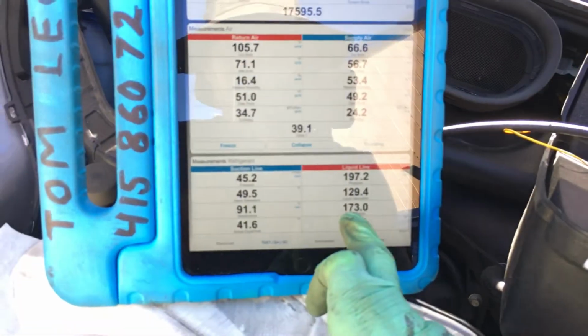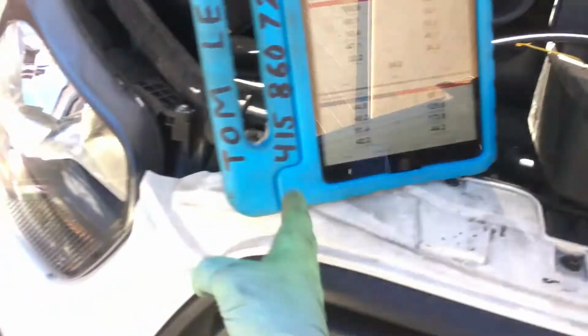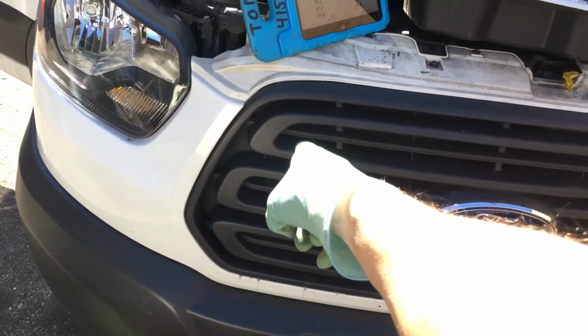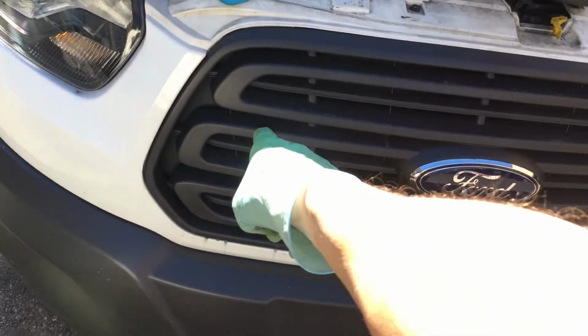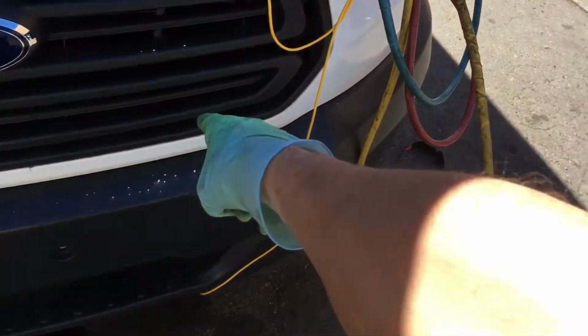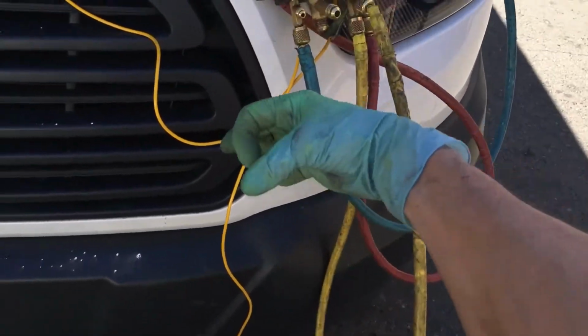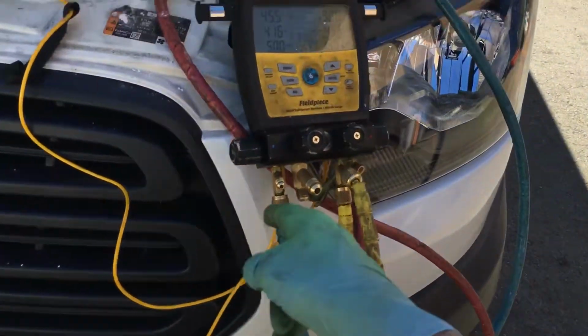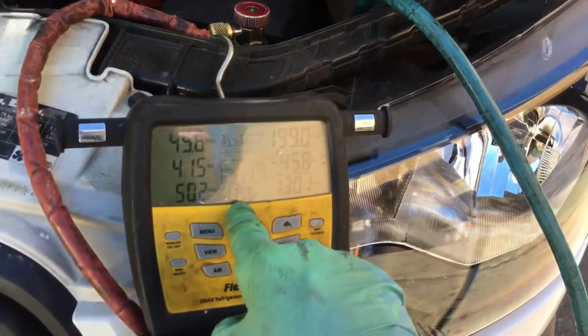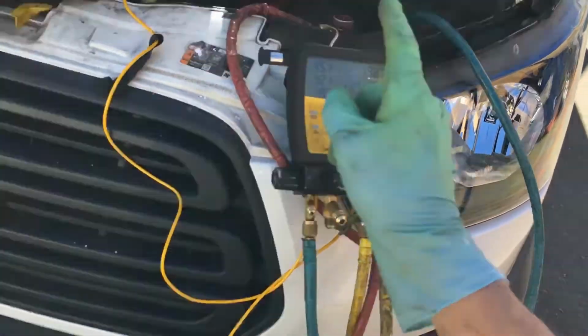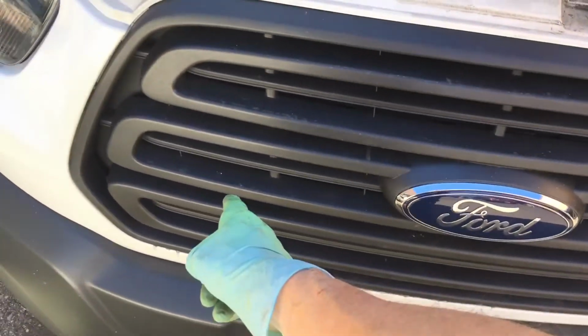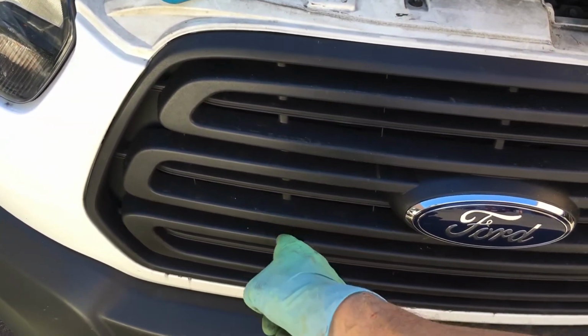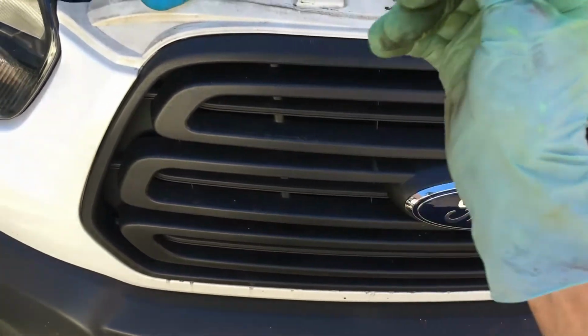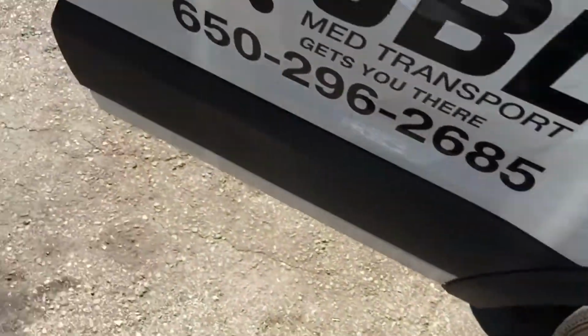Alright. This is not an easy vehicle to maneuver around, but it's not the worst. So our 173 degrees. So the compressor is located up mid-engine, way over here. Where I'm taking the temperature is the hot gas discharge line is going way down over here, and then it's dropping down at an angle, and that's where I clamped off to it. So I'm far away, and my liquid line discharge temperature is 173 degrees. So I could probably safely say that my hot gas discharge is 200 degrees out of the compressor, probably 250 plus inside in the core of the compressor.